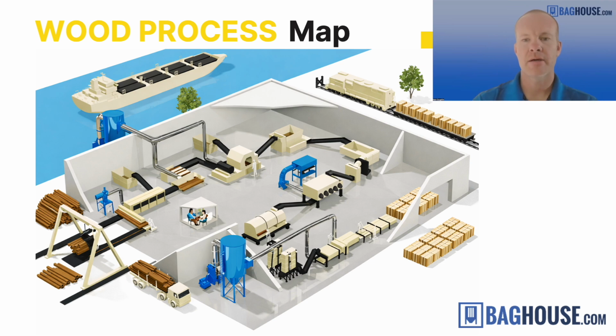On this slide you can see a general wood shop. You have a dust collector or a couple of dust collectors, and ductwork that pulls the collected dust from the processes - chop saws, miter saws, panel saws, polishing stations, all these places where dust is generated. You have collection hoods at each of those process pickup points, and engineered ductwork sized and designed to pull that dust out of your shop and through the dust collection system using a system fan or blower, then exhaust clean air either outside the facility or, potentially, recycle it back into your facility to maintain pressure in the building or help lower your heating and cooling costs. So that's a general wood shop, pretty typical elements we commonly see.